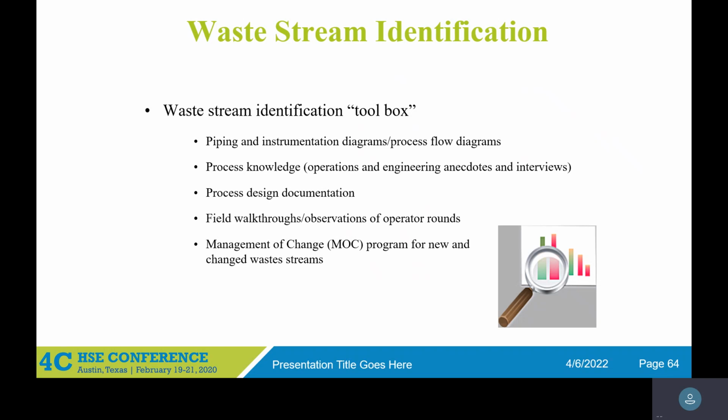For your programs, for waste stream identification, what we do is we highlight the P&IDs and where it first exits the process and then follow it all the way through. Same thing with waste management units. You want to highlight all the waste management units on your P&IDs and see what the control is. Keep that documentation. Robinson has it. We should have it, yeah.